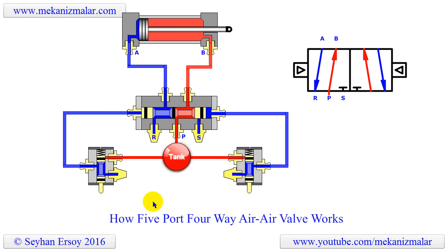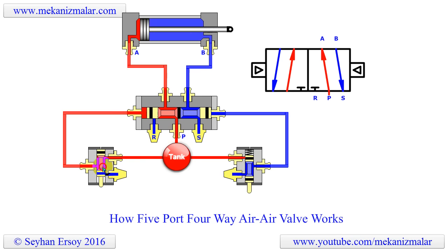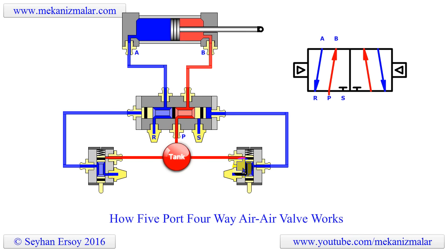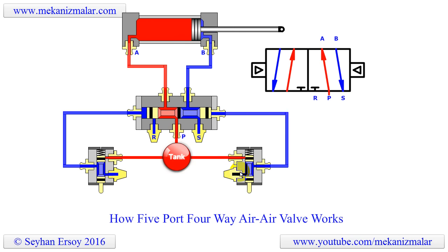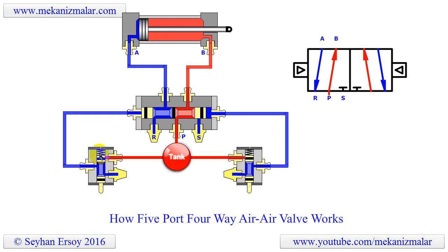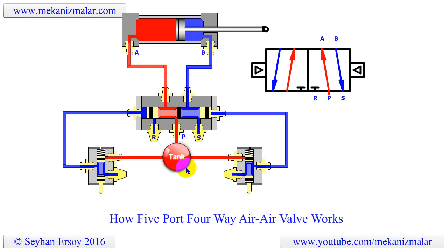Please note that we also have 2 similar valves at the left and right of the main valve. I call these valves 3-port, 2-way, force-to-spring valves. While the 3-port and 2-way descriptions will be obvious based on the previous description, the force-to-spring term needs an explanation. It means that we can actuate the valve by force — by pushing the button on the valve — and it returns to its previous condition by spring when the force is removed from the button. The force condition is emulated in this animation by mouse clicking on the valve, and the mouse release action emulates the force being removed from the valve button.